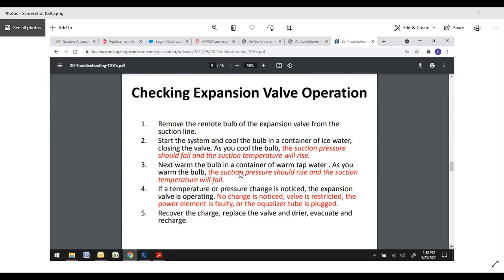For years, we just put it in our hand, hold it and run outside and check. But you can also put it in a little glass of warm tap water. At that point, your suction pressure should rise dramatically and your suction temperature will fall. So if you get little to no rise when you're going to the extremes of ice water and warm to hot water, then you've got a bad expansion valve. It's probably in your bulb that's not allowing it to sense. So if a temperature or pressure change is noticed, the expansion valve is operating. If you go from normal to super cold, it should be a dramatic change. If you get like a 5 psi change, you've probably got an issue with the sensing bulb. For sure, if you get no change at all, then it's definitely got an issue.